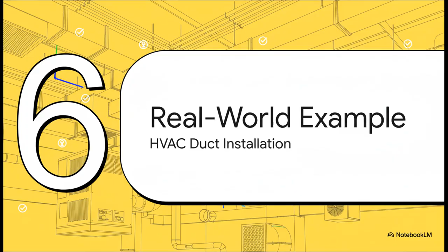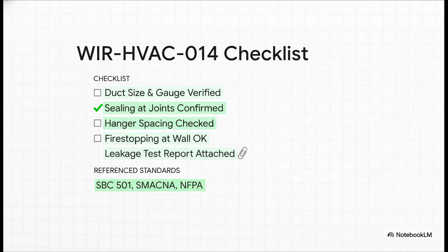Okay, check this out. We've got WIR HVAC 014. The engineer has ticked off everything: duct size and gauge, verified. Sealing at the joints, confirmed. Hanger spacing, 1.8 meters, checked. Fire stopping at the wall penetration, looks good. Leakage test report, attached. And look at this, they've referenced the specific codes, SBC 501, SMACNA, and NFPA. Now that is a solid, defensible WIR.